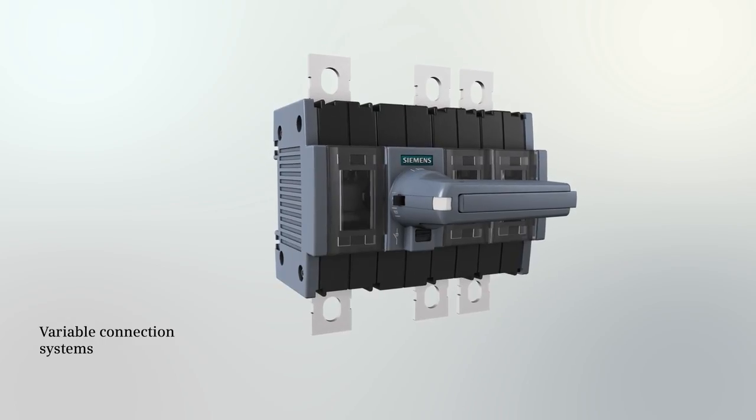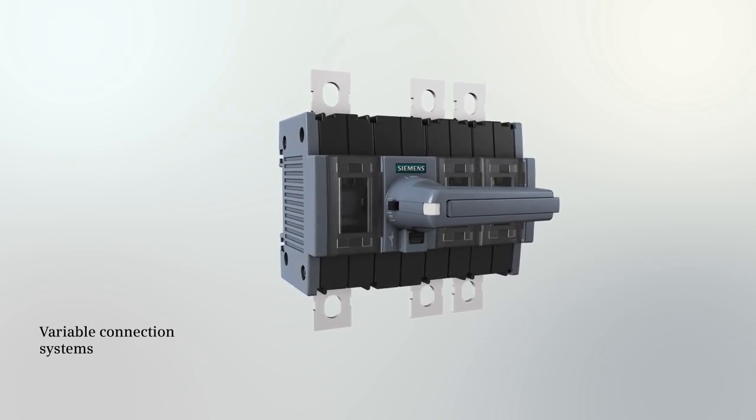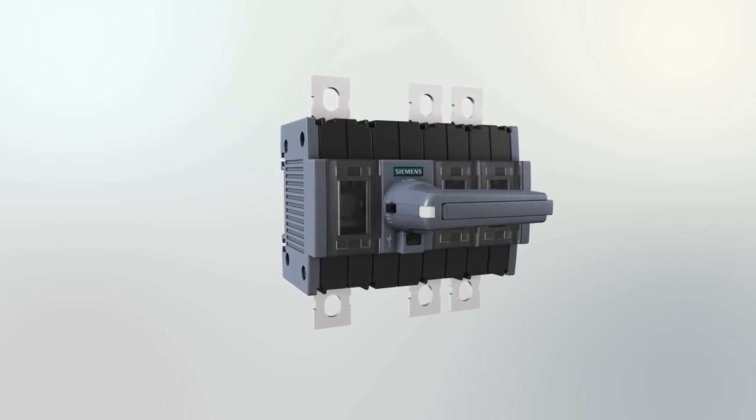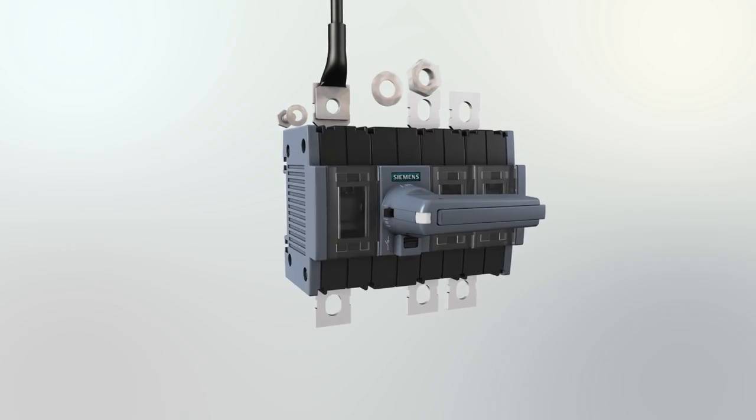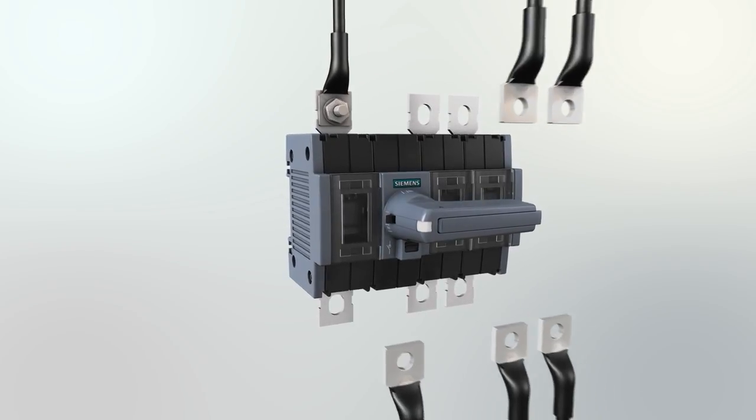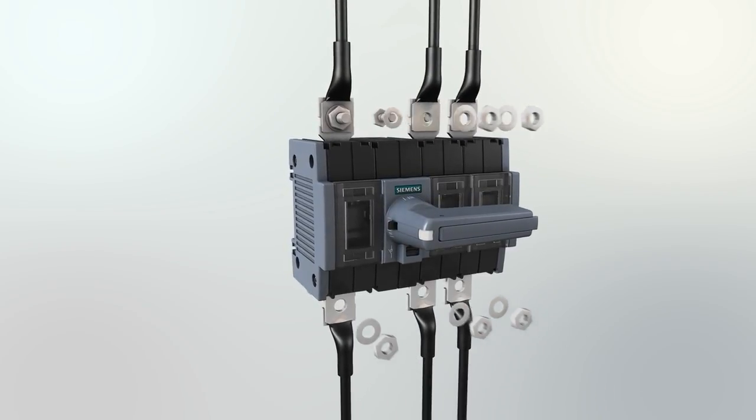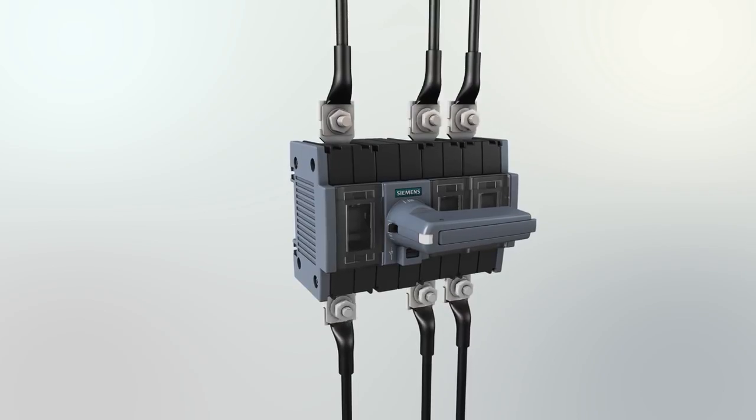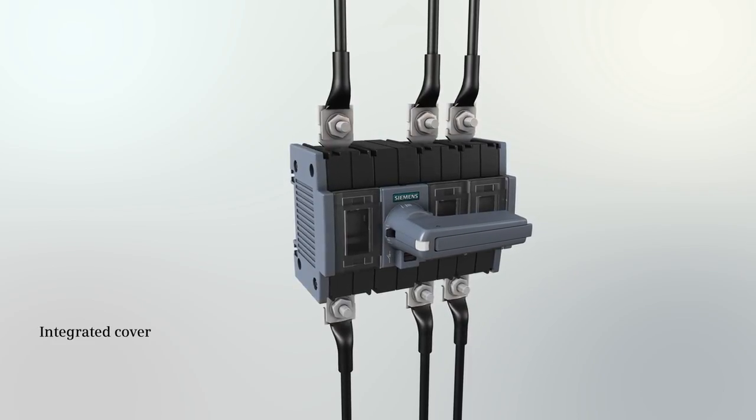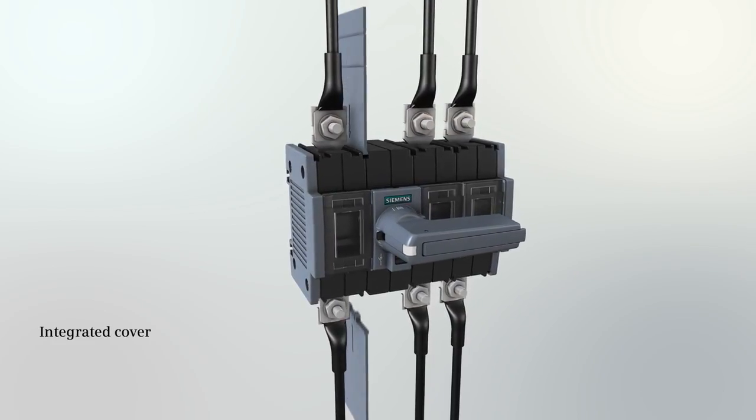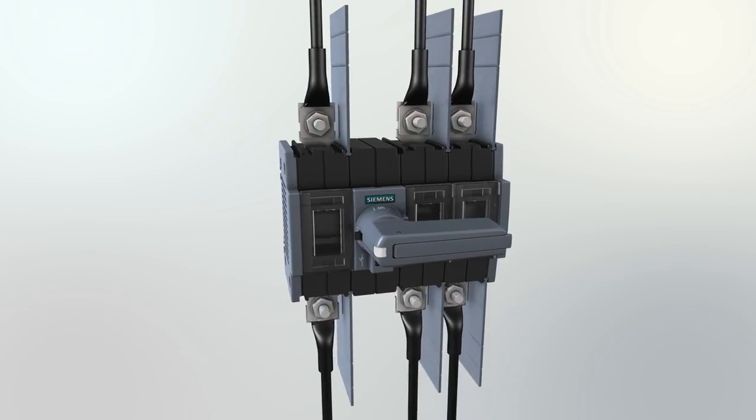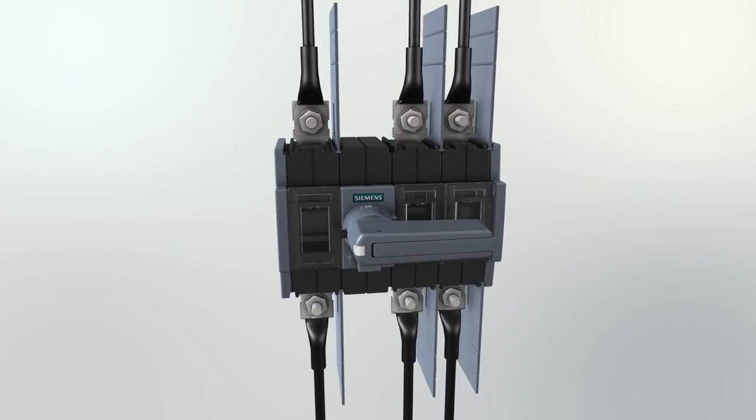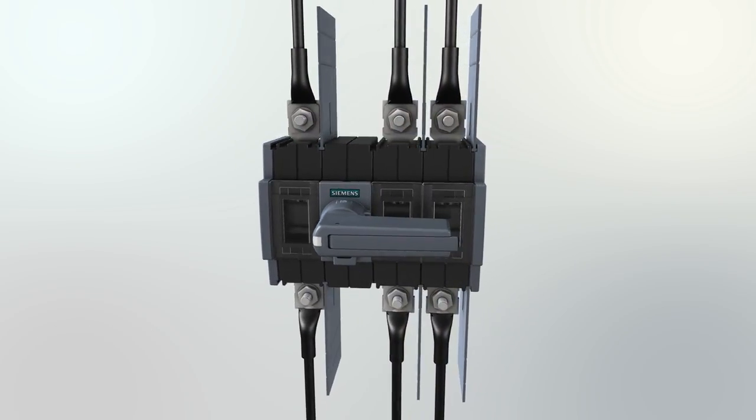The 3KD switch disconnectors can be connected in various ways. Starting from a rated current of 80A, they are available with flat terminal for cable lugs or bus bars. For long uninsulated cable lugs or bare copper bus bars, phase barriers provide protection against interphase arcing.